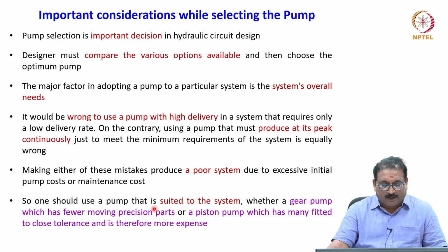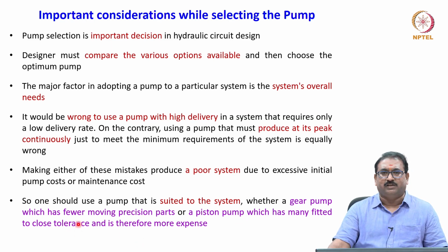whether I should use a gear pump, which has fewer moving parts and is not so precise compared to the piston pump, or I should use a piston pump, which has a large number of moving parts, all with close tolerance. Due to this, it is more expensive as compared to the gear pumps.